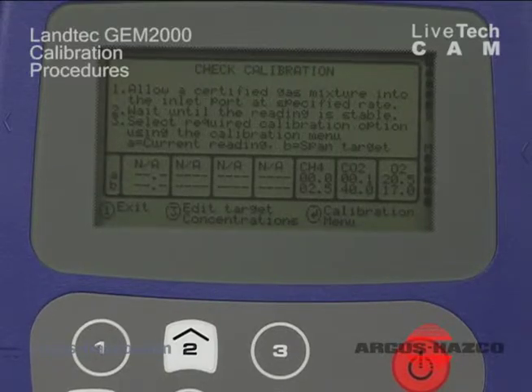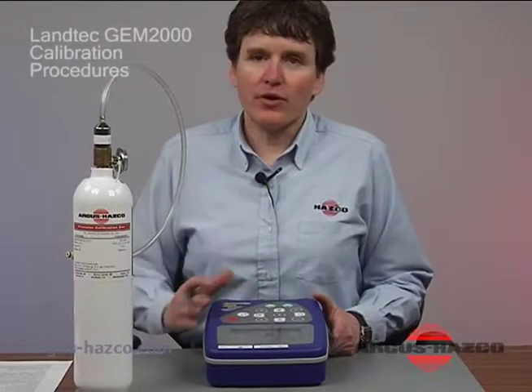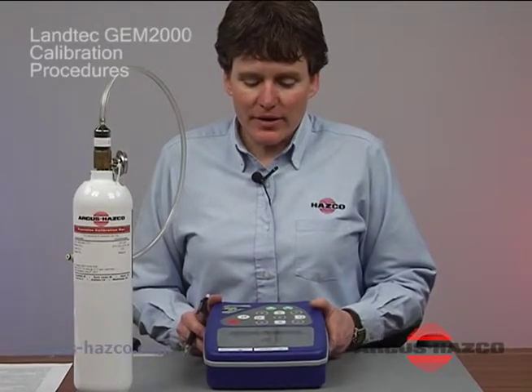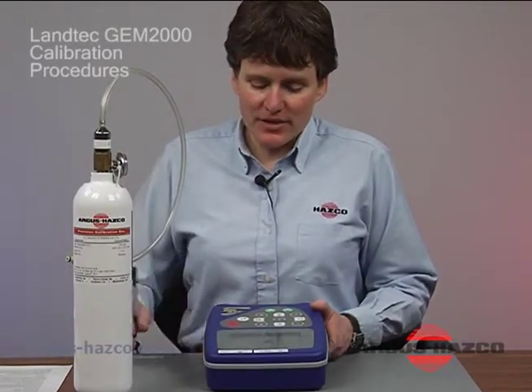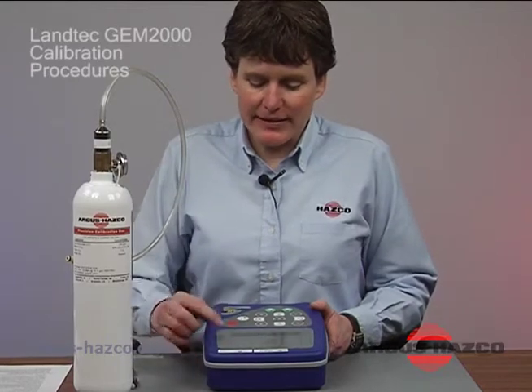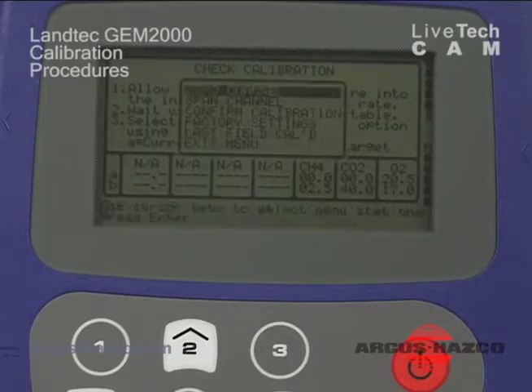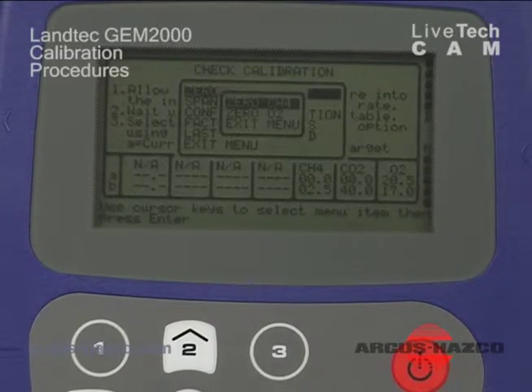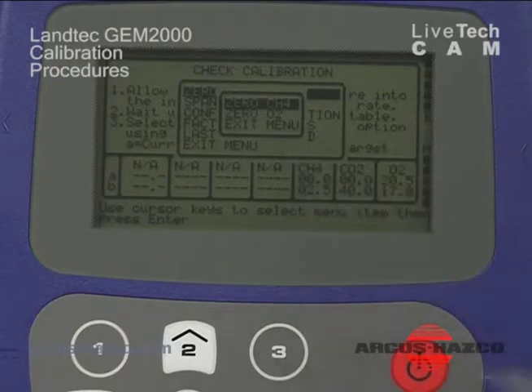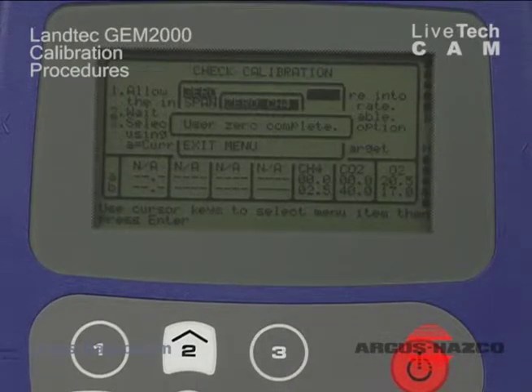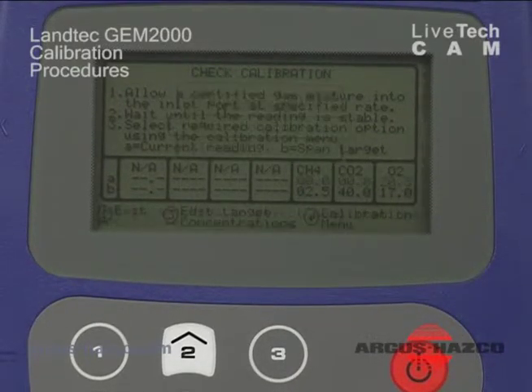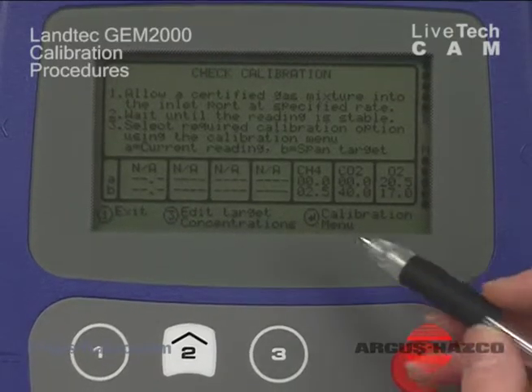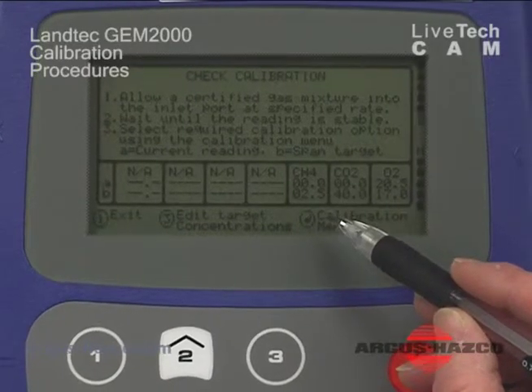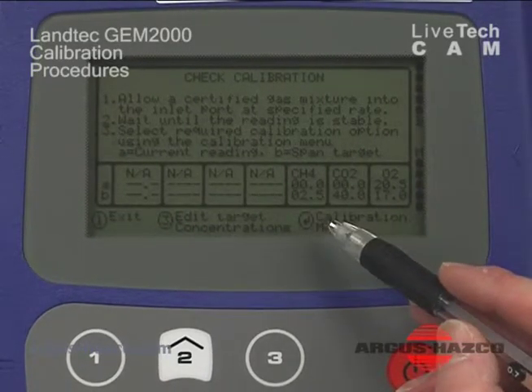We let the pump run for a while. We let the air flow through the unit. And when we're satisfied with our 0 gas reading, we go ahead and hit my Enter button. I want to 0 that channel. I hit Enter again, and 0 CH4 pops up. I hit Enter again, and my CH4 methane has been 0'd. Now my next thing would be to perform a span calibration on my CH4 channel.